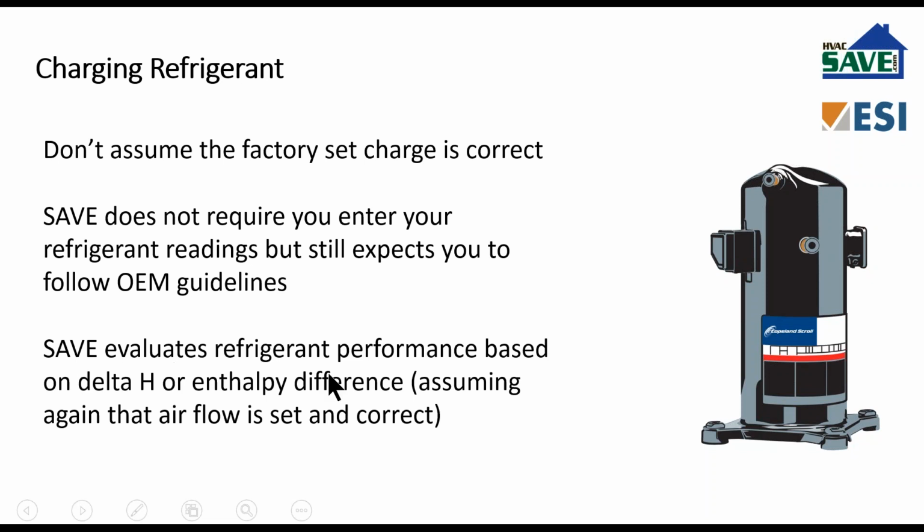Rather, SAVE evaluates refrigerant charge performance, again, capacity, efficiency, lower performance, all together taken as one, based upon the delta H or the enthalpy difference. Again, assuming that airflow is set and correct. I'll touch on delta H again a little bit later on.